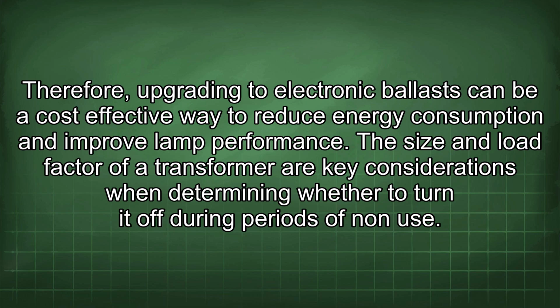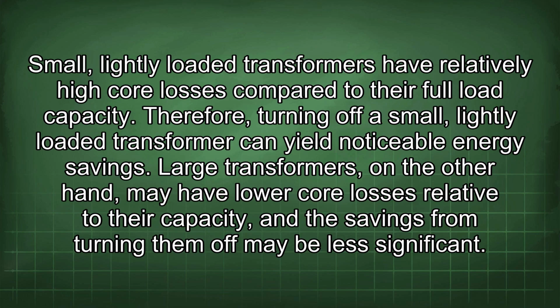The size and load factor of a transformer are key considerations when determining whether to turn it off during periods of non-use. Small, lightly loaded transformers have relatively high core losses compared to their full load capacity. Therefore, turning off a small, lightly loaded transformer can yield noticeable energy savings. Large transformers, on the other hand, may have low core losses relative to their capacity, and the savings from turning them off may be less significant.